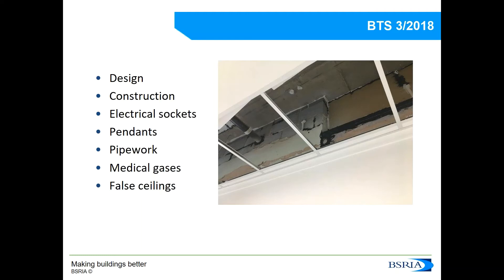We would have to pay attention to and seal things like windows, viewing windows into the isolation rooms, electrical sockets, water pipes, pendants, pipework, and medical gases. When it comes to false ceilings, as you can see here, the air permeability levels will be determined by the envelope area including the area above the false ceiling, unless the false ceiling is completely sealed. What you see in this picture is that we lifted some ceiling tiles and saw that the envelope above the false ceiling needed to be resealed to achieve the necessary airtightness.